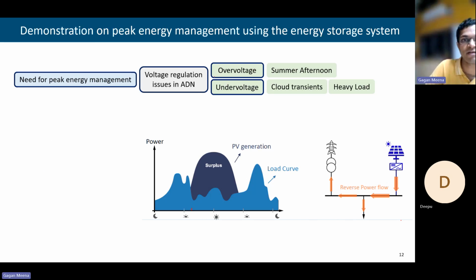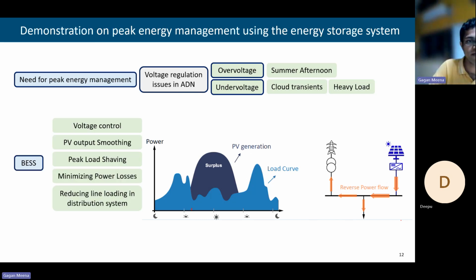Okay, yes. So here we have voltage regulation issues in the active distribution network. Over voltages occur in the summer afternoon, when the load is less and the PV generation is quite high. Under voltages occur when generation is low and load is more. This happens when there is cloud cover and the output of PV reduces. In a heavy loading condition, when load is quite high, more than the generation, there will also be under voltages. Cloud transient and heavy loading.